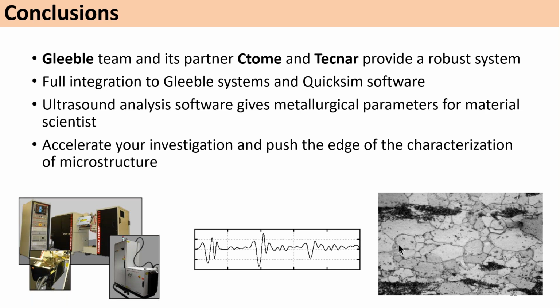Okay. Let's see, a few more questions here. How sensitive is the Lumet signal to the surface roughness of the sample or thin surface oxidation? Yeah, that's a great question. So it is recommended before a test to have a sample which has no oxide scale from the hot rolling, because this tends to reduce the reflectivity of the light and therefore reduce the amplitude of the signal that we measure. So it's often a good idea to polish the sample or to have a sample machined which has no oxide scale from the hot rolling.